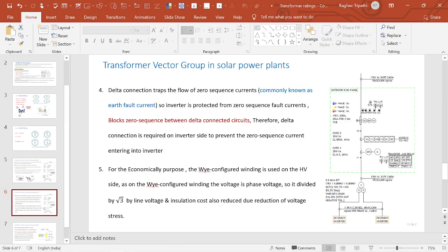The reason for using star winding on the transmission side: for economical purposes, the Y-configured winding is used on the HV side because the phase voltage equals the line voltage divided by root 3. When voltage is reduced, voltage stress reduces, insulation cost reduces, and we can have a reduced overall cost of the transformer. That is why star connection is taken for economical purposes.